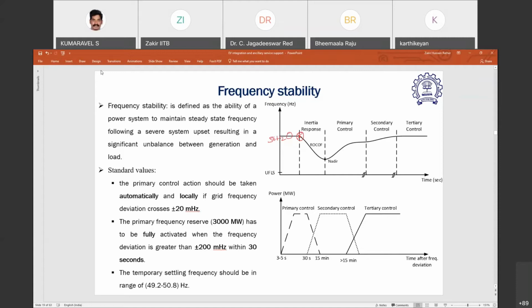Governor control, which will actually act in those generators which do have a margin, of course, first it should have a margin. The governor control will kick in only after 2-3 seconds, because governor control works based on the frequency of the grid, on the speed of the machine. So what will it do? It first needs to detect the change in the frequency in the grid. Then it needs to send the signal to the governor controller. And then the governor controller will send the command to the steam valves, if it is a steam power plant. Steam valves will open through the servo motors, which will take its time. There is a time constant associated with all this, and then the power plant will actually start increasing.